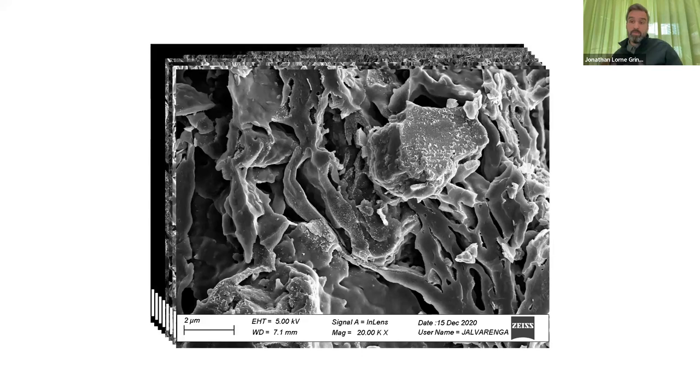And so for evaporative cooling, this is going to be good. It's going to create a porous matrix to hold water. And then at the surface, we'll have a thin film that will evaporate off that water, inducing cooling. And that's good in a typical dry environment, but we want to be able to separate out the latent cooling with that evaporation from the sensible cooling, to be able to bring cool, dry air into the building without that extra moisture content of a typical swamp cooler.